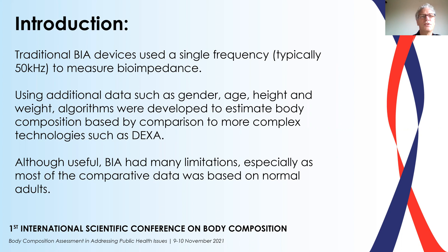I'll introduce you to the traditional BIA devices which used a single frequency, which was typically 50 kHz, to measure bioimpedance. Using additional data such as gender, age, height, and weight, algorithms were developed to estimate body composition based on comparison to more complex technologies such as DEXA. Although useful, BIA had many limitations, especially as most of the comparative data was based on normal adults.